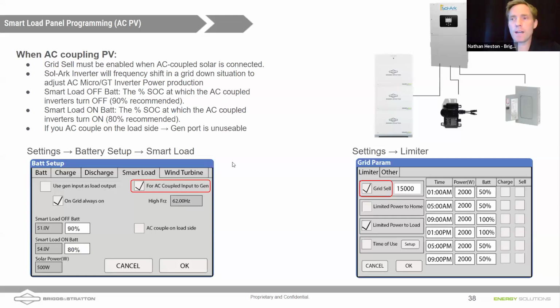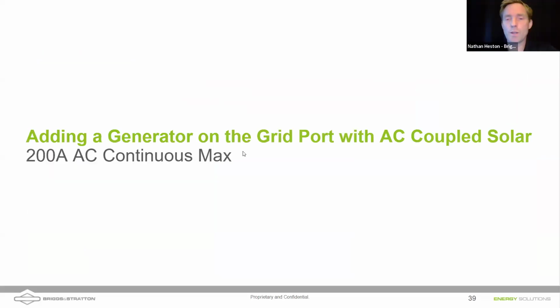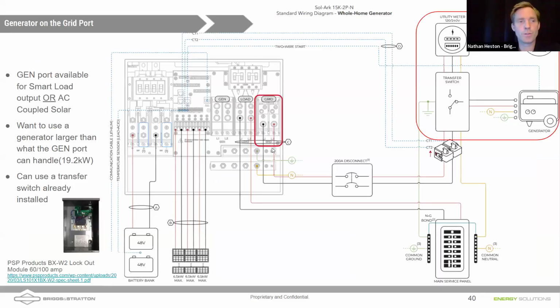And I don't know the exact, Daniel, do you have that memorized? The exact power output? Is it at 61 hertz, it drops it to 50%? I don't have it memorized. Okay, but that's essentially what that solar converter can do. Because it's no longer tied to a real grid, it's grid forming, it can adjust the frequency to slow down those microinverters.